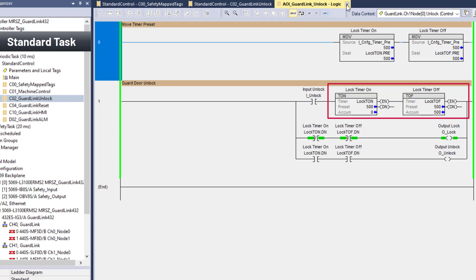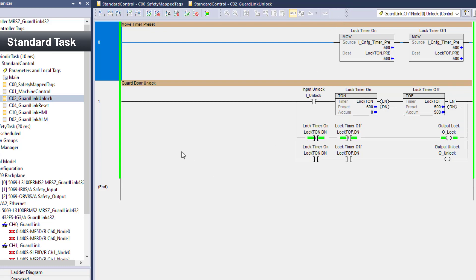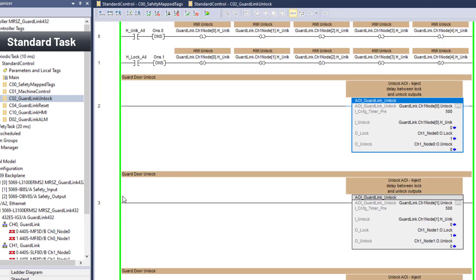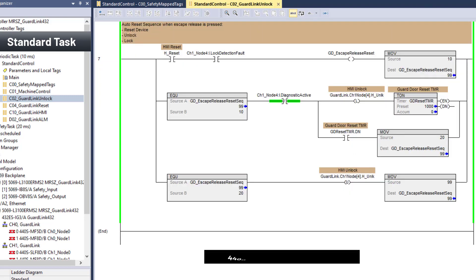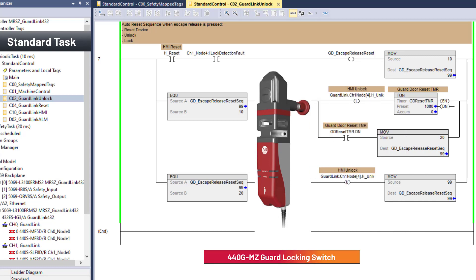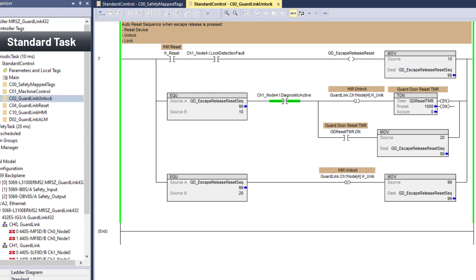There is an AOI GuardLink unlock for each locking guard door. The GuardLink-enabled Series B 440G-MZ guard door detects when it has been forced open, either with the escape release or an external device. To recover from a lock detection fault, the device is reset, unlocked, then locked.